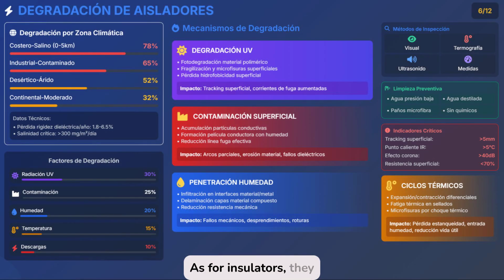As for insulators, they are essential but often overlooked components, whose degradation can lead to serious electrical failures and considerable economic losses. Although they are not as prominent as transformers or switches, their role in electrical insulation is key. When they lose their properties, partial discharges, loss of dielectric strength, and unexpected disconnections can occur, resulting in service interruptions and costs due to penalties or emergency interventions.